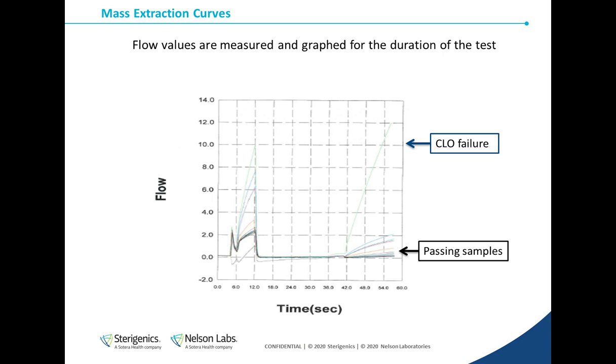Here are some graph examples of typical vial test data. The flat part at the front of the curve is the gross leak check. The larger of those 2 peaks that follow is the large leak check. The long flat line is the stabilization phase, and the rise at the end is the fine leak check. The CLO value in these graph examples is about 12, and this would be a 2 micron defect. And you can see here that all the passing samples have values of 2 or less.